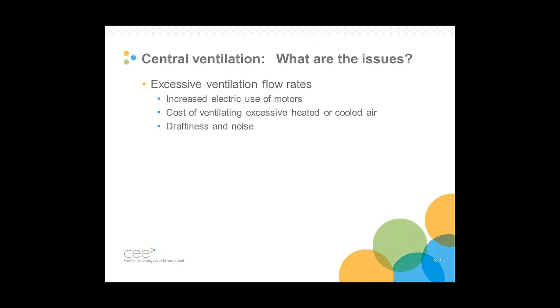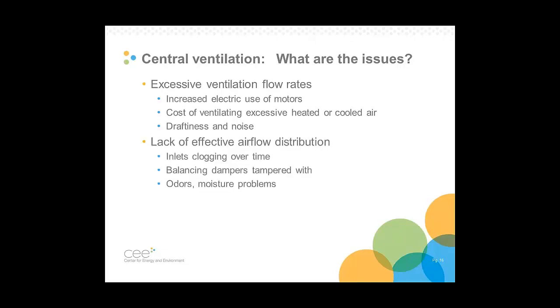So what are the issues with these systems? The primary energy issue is that there can be excessive ventilation flow rates. Basically, they're ventilating more air than they need to be ventilating. There's an electric cost from the motors running these systems. There's the cost of ventilating excessive heated or cooled air, and then the comfort issue with excessive ventilation, which can be draftiness and motor noise, or duct noise.